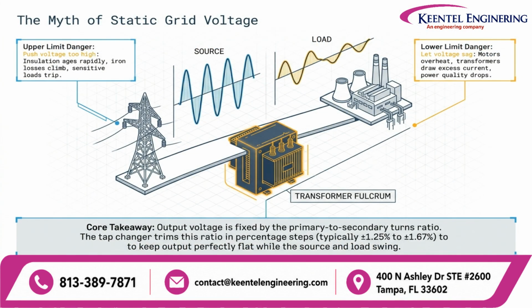A common misconception is that electrical grids operate at a constant voltage. In reality, power system voltage continuously changes due to load variations, renewable energy fluctuations, industrial demand, and transmission constraints. During peak demand, voltage naturally drops because more current flows through transmission impedances. Conversely, during light loading or high renewable generation, voltage may rise above its desired value. The transformer tap changer acts as the grid's automatic balancing mechanism. By adjusting the transformer turns ratio, it compensates for these voltage variations and keeps customer voltage within acceptable limits. Without this capability, voltage instability would become a serious operational challenge across modern interconnected power systems.